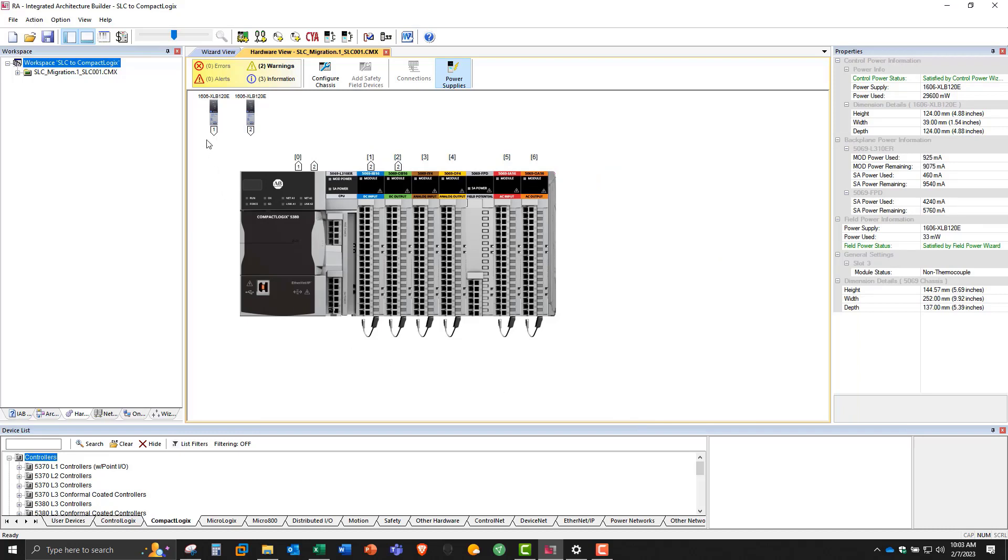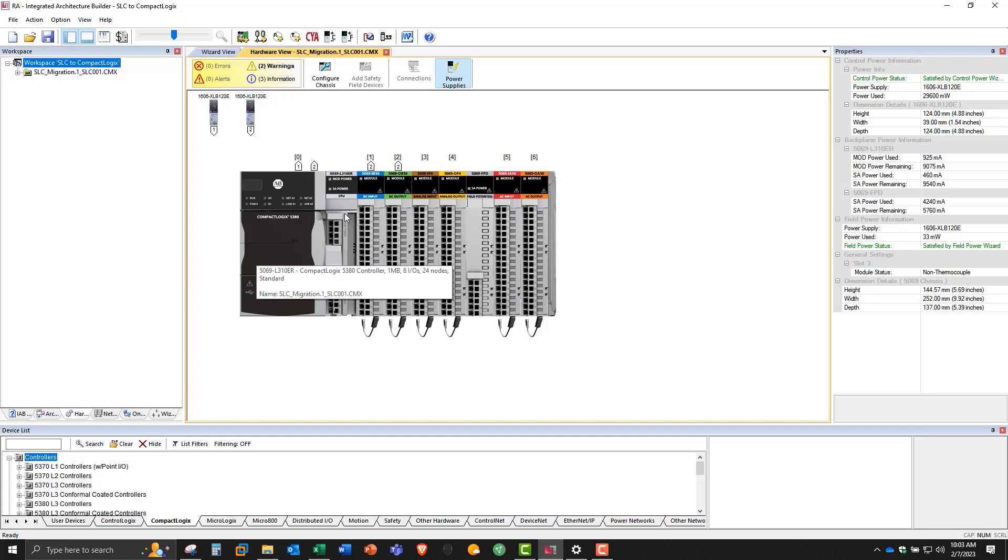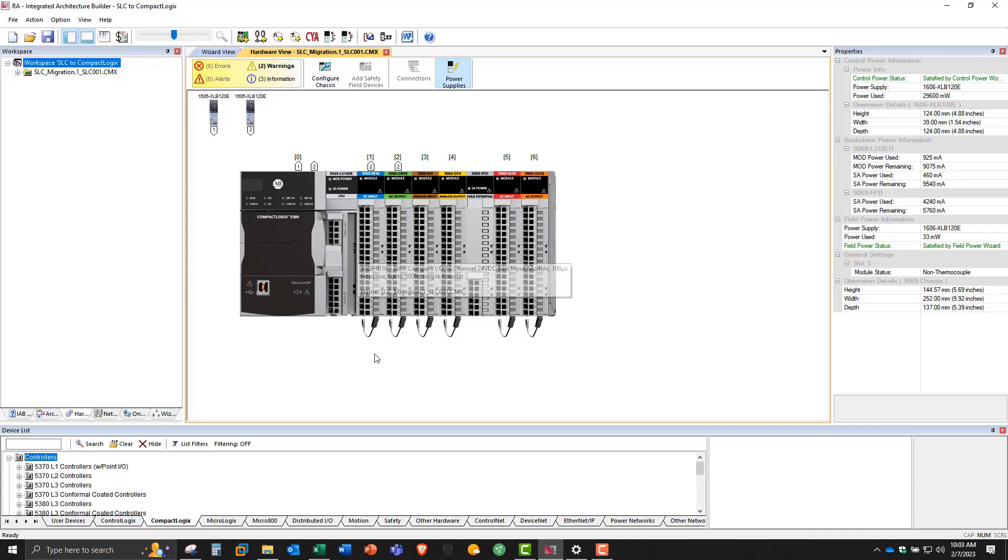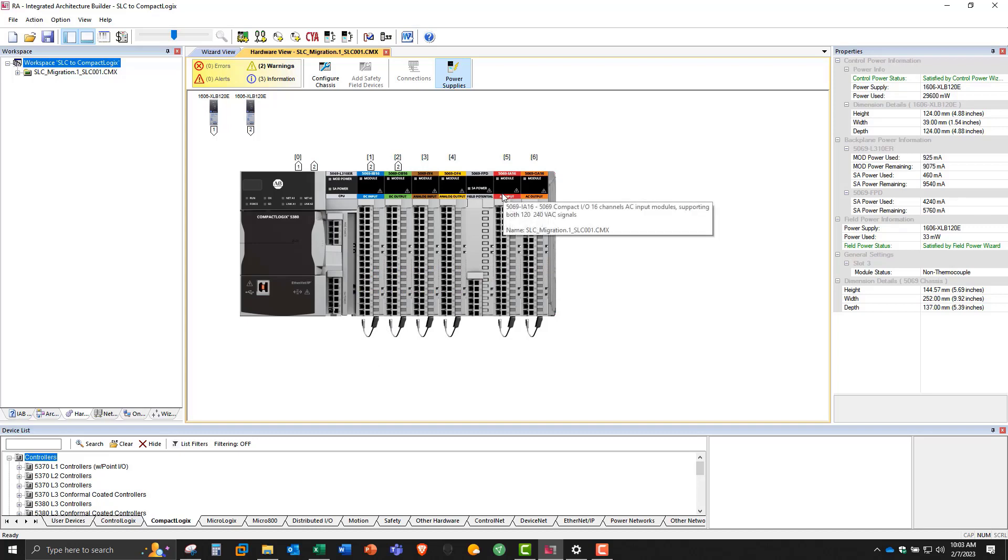Now some people may be asking, well why do you have two power supplies here? Well, Rockwell recommends having a separate power supply feeding the module power terminal block, and one for the SA power block. Because there's two different bus systems on here. The MOD power basically powers the processor itself, and then the circuitry for the IO cards. And SA sensor actuator is your field power, and that's a separate bus that runs along the bottom.